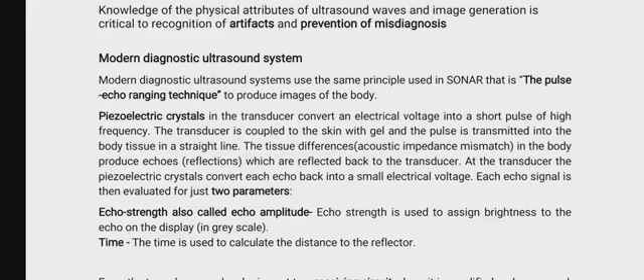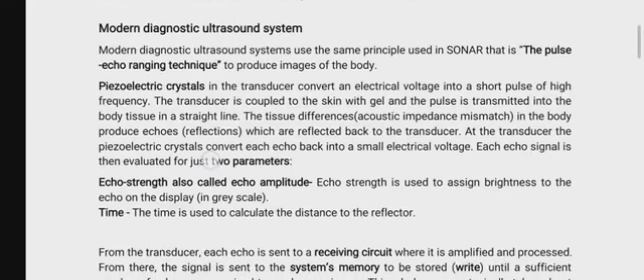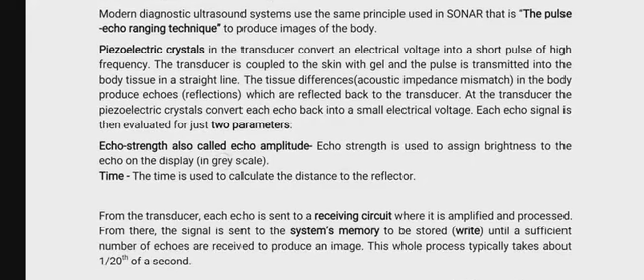Now, piezoelectric crystals in the transducer convert an electric voltage into a short pulse of high frequency. The transducer is coupled to the skin with gel, and the pulse is transmitted into the body tissue in a straight line. The tissue differences, that is the acoustic impedance mismatch in the body, produce echoes, that is reflections of those sounds, which are reflected back to the transducer. At the transducer, the piezoelectric crystals convert each echo back into small electrical voltages. Each echo signal is then evaluated for just 2 parameters.